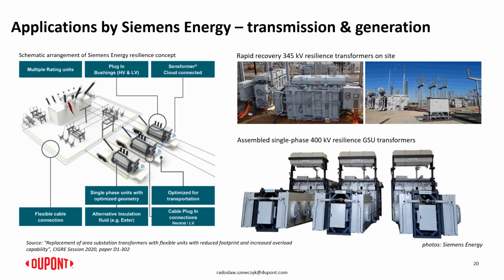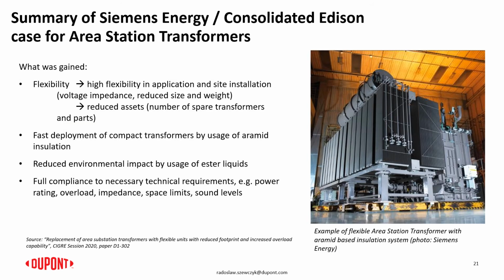The solutions for the generator step-up transformers were also developed up to 400 kilovolt class. And we still continue those developments, and in this case with Siemens Energy and Consolidated Edison, there is a series of transformers already built and installed, and we continue those considerations for area station transformers where the units would have higher flexibility on the loading or the location for the installation of the transformers. So these transformers with the multi-voltage ratings and increased overload capability, they are enabled by use of alternative insulation systems.